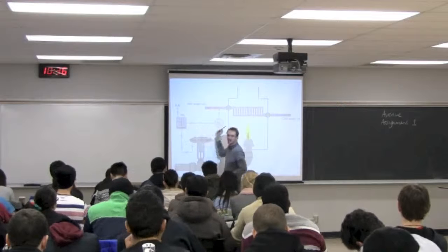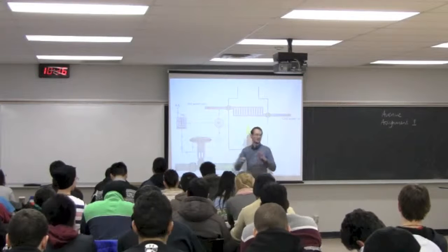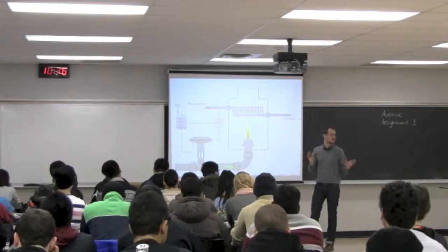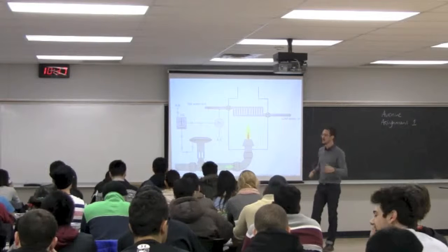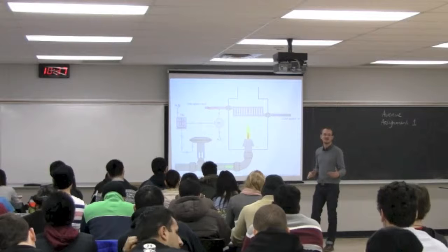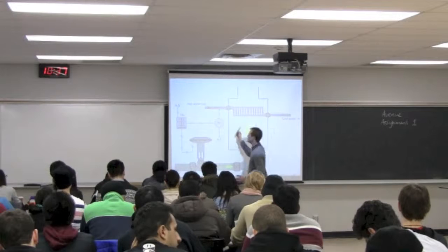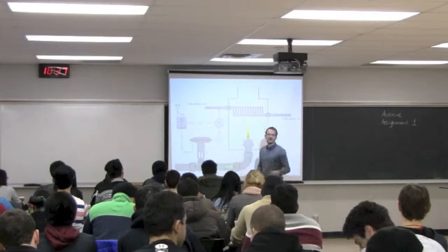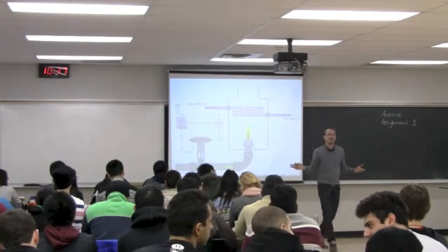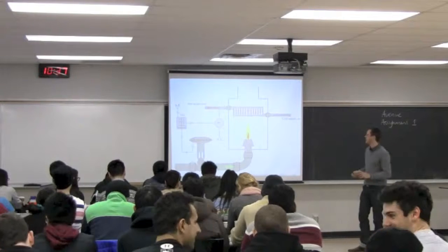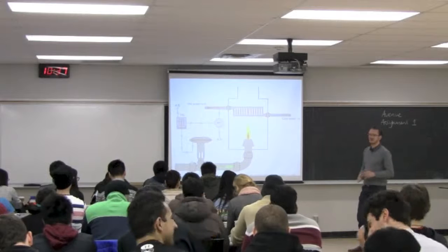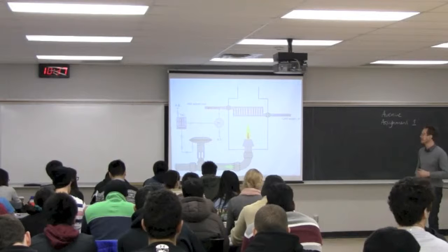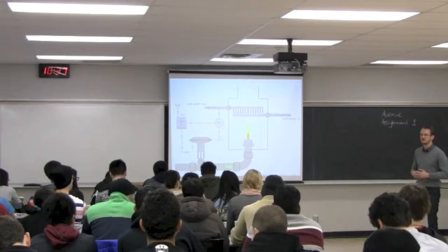Or we could replace it with an electronic signal. So you send a low number of millivolts or a high number of millivolts. You'll see this in all the plants. Many people will work in established plants that were built in the 60s, 70s, and 80s. They will use air to transmit the signal. Newer plants will use an electric circuit. Even newer plants will be all wireless, so wireless transmission to some centralized system. But there are issues with reliability on wireless signals, so we don't see that a lot, especially on critical variables.